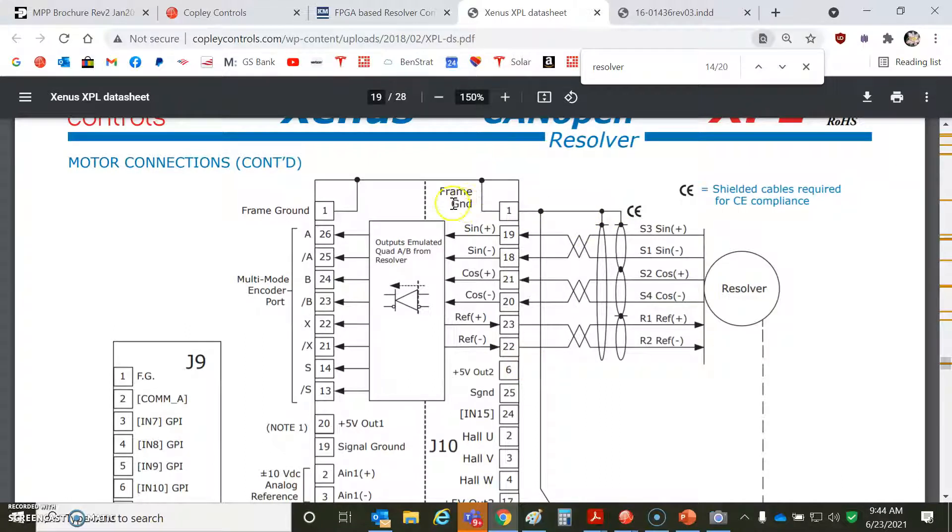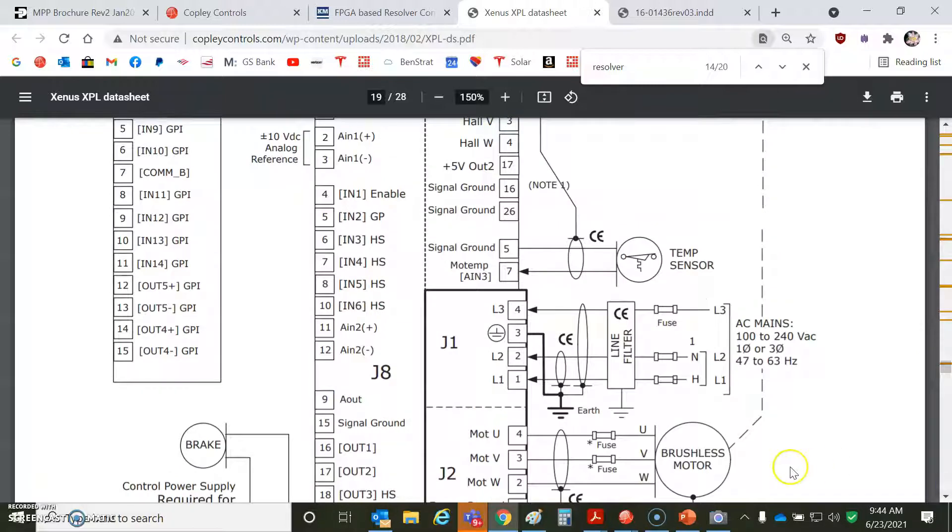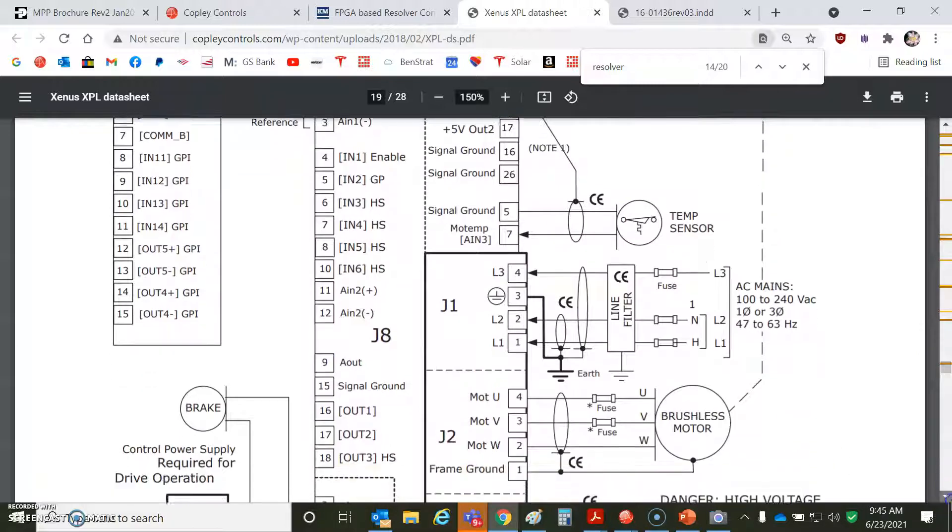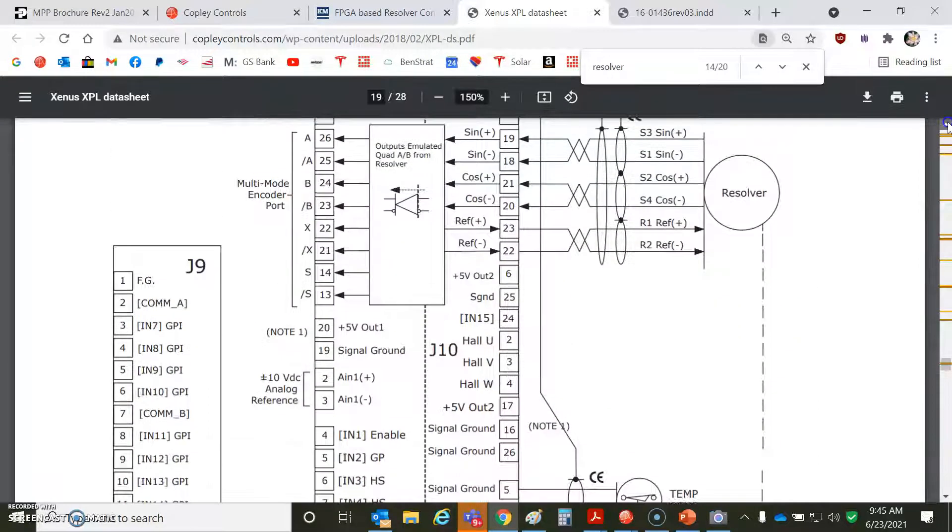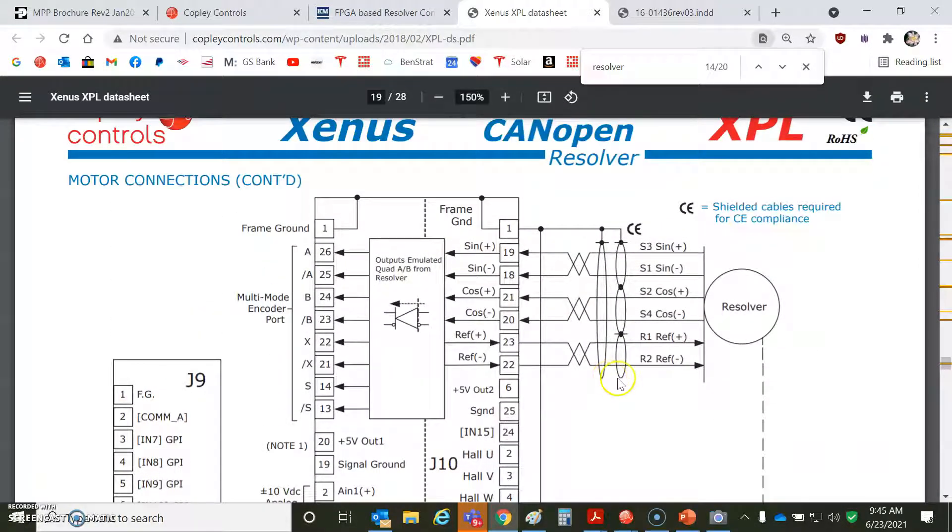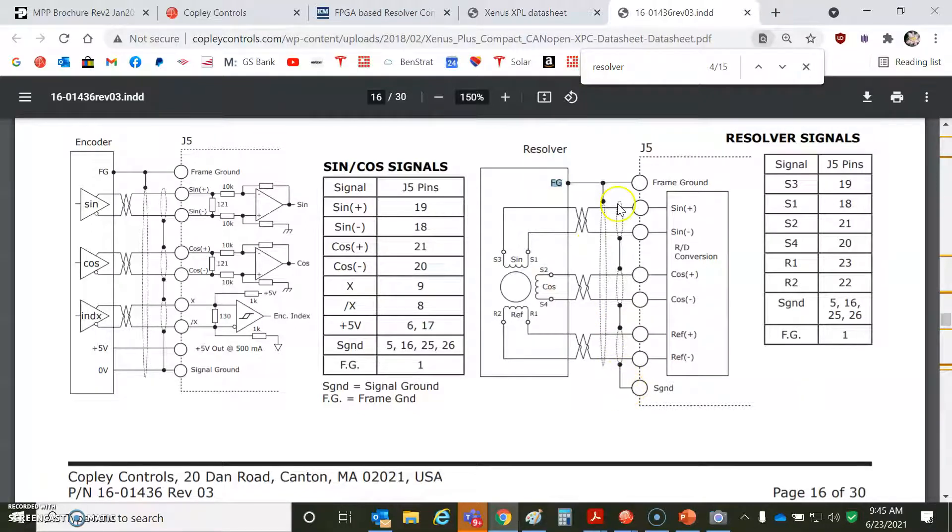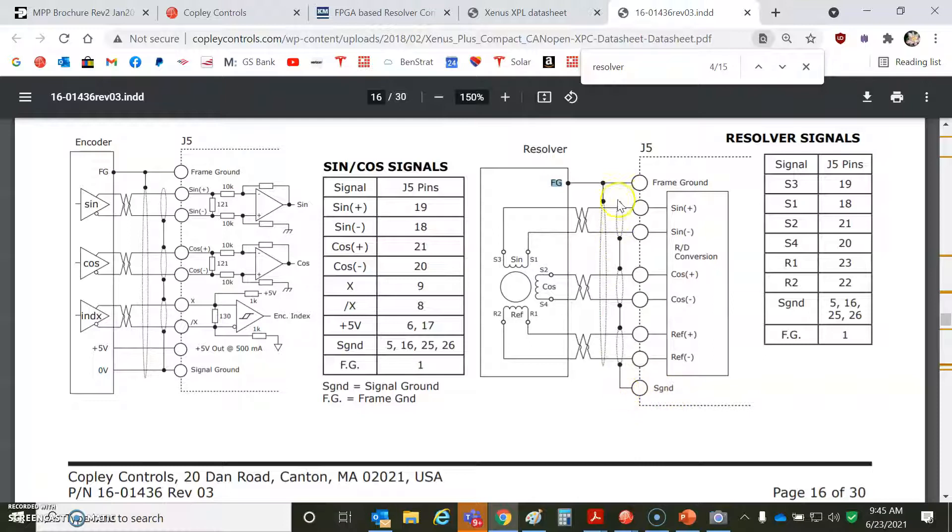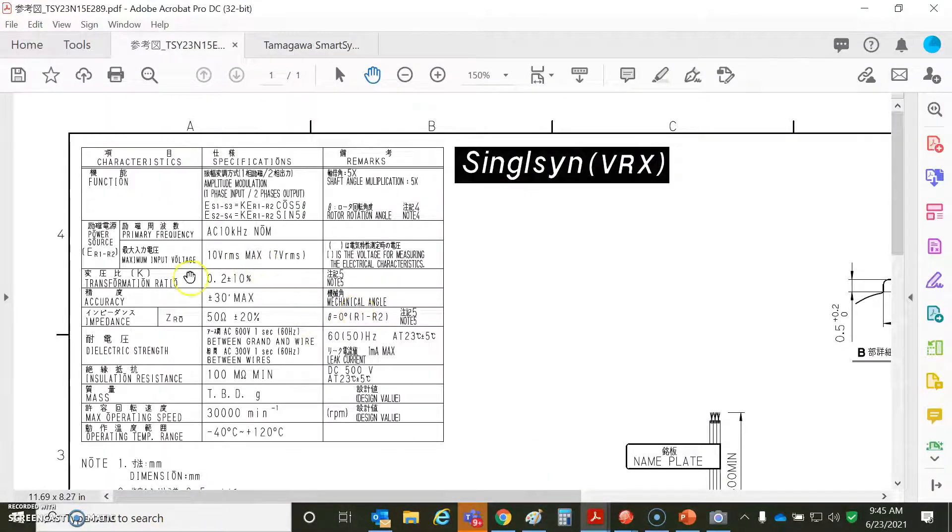So just a note on the wiring, we show the shield, the outer braid connected to the frame, nothing connected to the motor case, which is a good way to do it. The motor finds a path to earth, of course, through the green-yellow wire that goes to frame ground. So the case finds a path to earth, but not through the feedback shield. I would propose that the inner shield get connected to signal ground. So we show this in some of the more modern inner foil shield, twisted pairs, individually shielded signal ground. It doesn't matter. Usually it's just a single braid or a foil with a wire and just don't connect it to the motor case. So I'll put a big red X here.